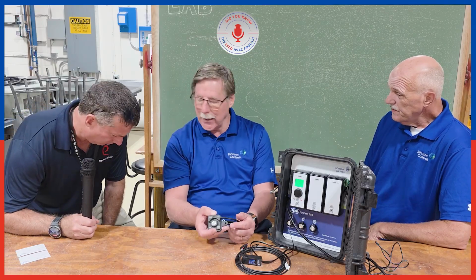So two things here. One, a lot of these sensors look alike, but this one is actually powered by 24 volts, constant, and it's a Modbus sensor. It's fully communicating. So it will only work with System 550. It requires a 24 volt sensor supply and it requires a Modbus communicating sensor.